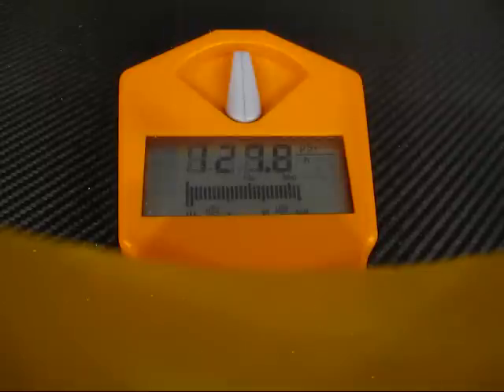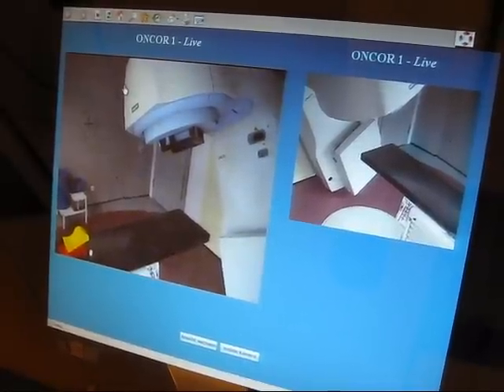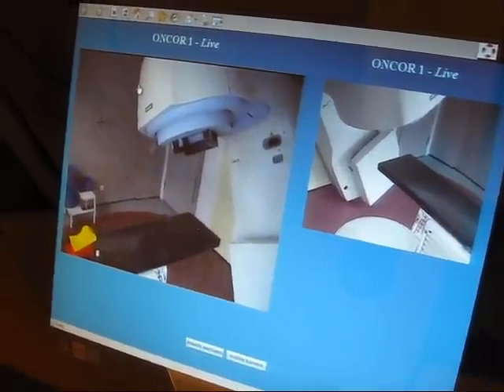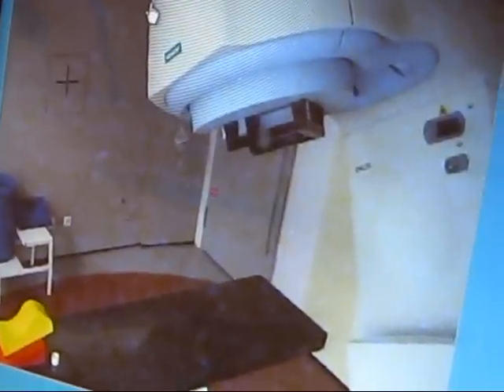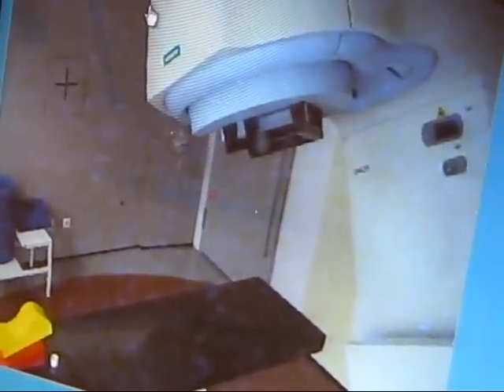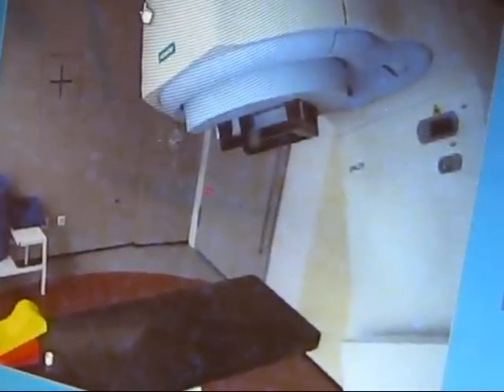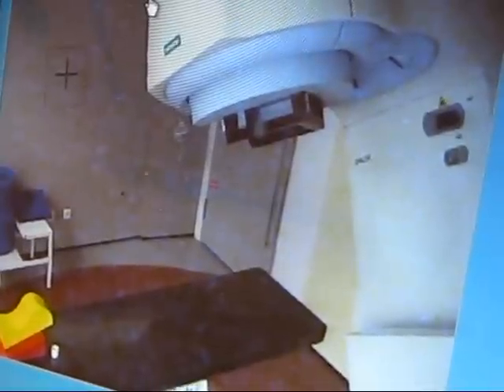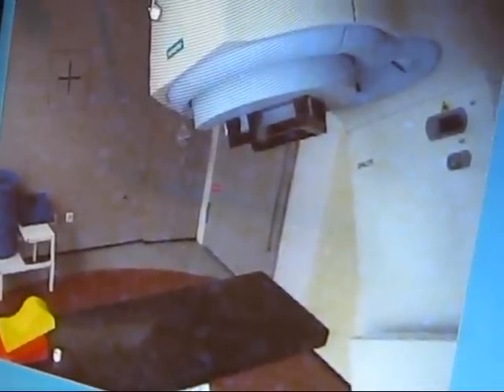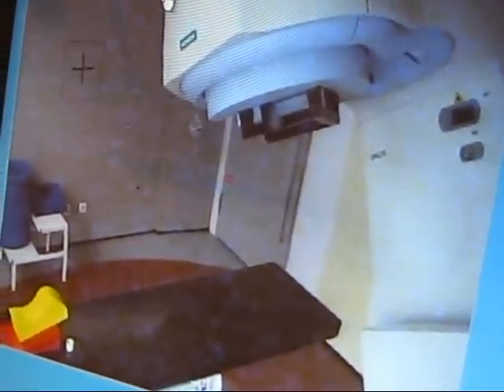Irradiation has started and you can see little flashes of radiation striking my poor camera, as well as the camera in the control room, of course, where you can usually monitor a patient that is being irradiated. Here you can see all these flashes of radiation and maybe you can also see that you have some dead pixels on that camera CCD. That is because of very high energy proton and neutron radiation that damages those cameras. So they need to be replaced every now and then, depending on the usage of the linear accelerator.